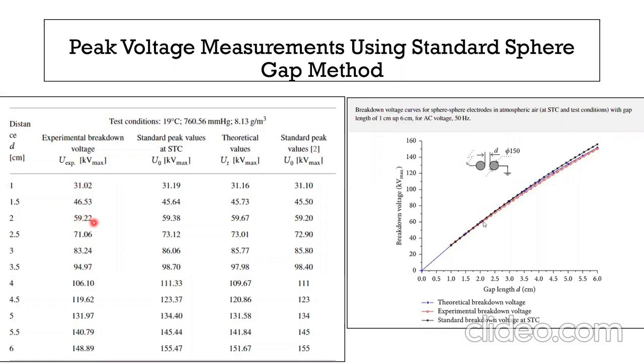You have one sphere at the top and you're pushing the sphere at the bottom upward. At a certain spacing there will be a breakdown of the air because all Townsend's theory and everything will come in picture for a specific space. As soon as the sparking occurs, your motor will stop. So you have to measure the distance, and some kind of system will display the distance. Then you have to look up this calibration.